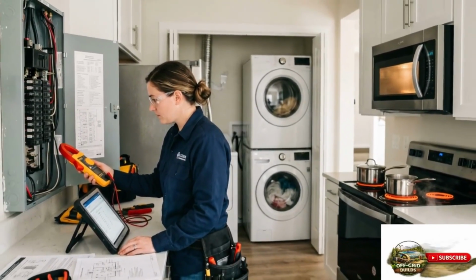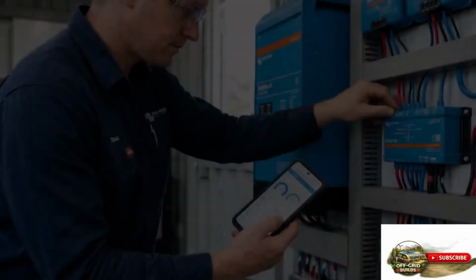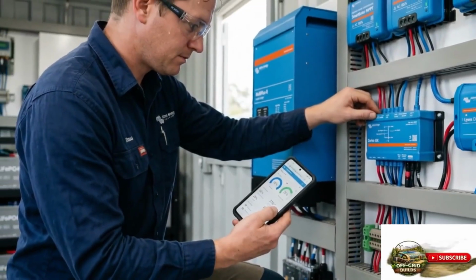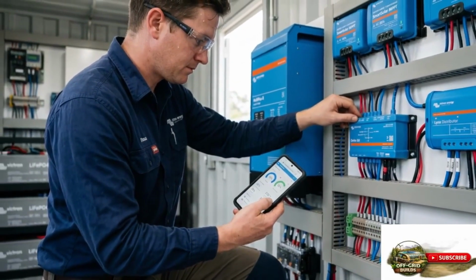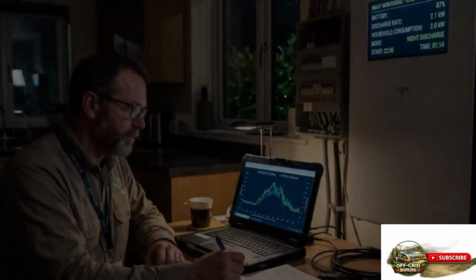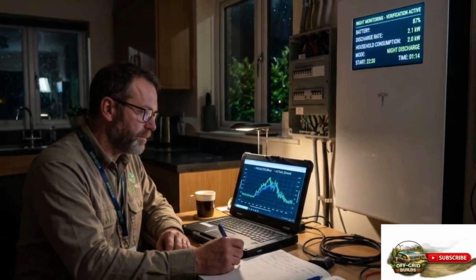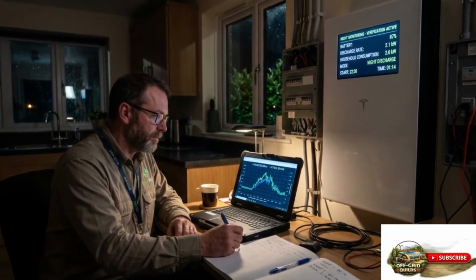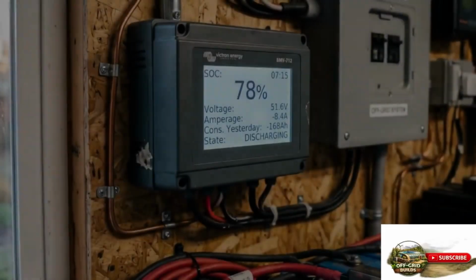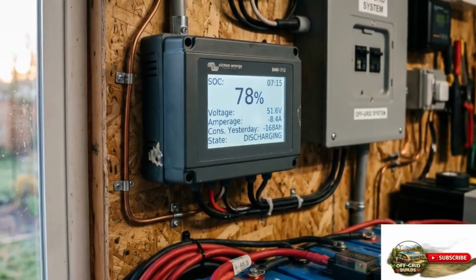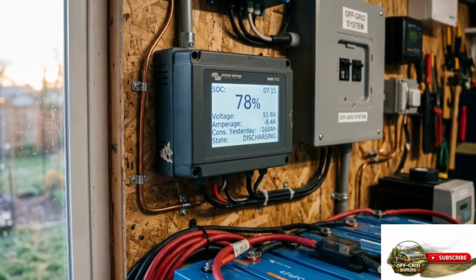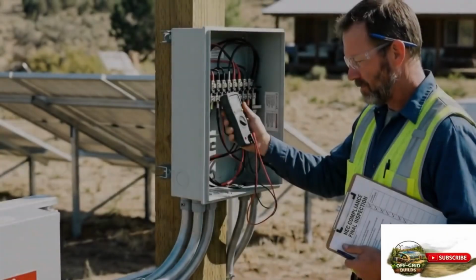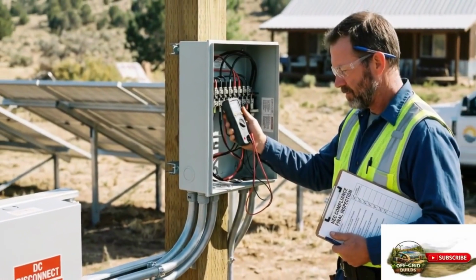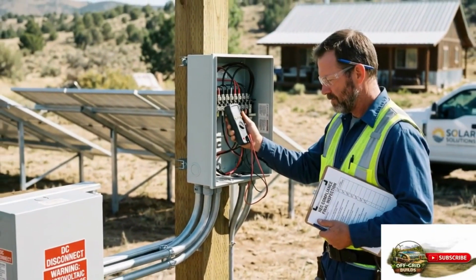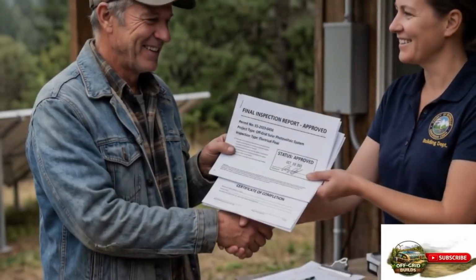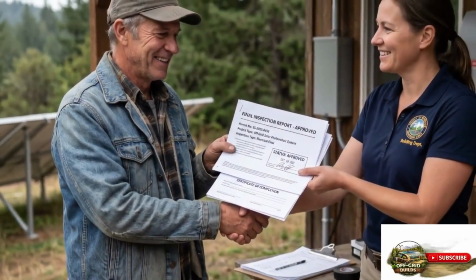Here is the mistake I promised at the beginning of this video, and it is responsible for more failed off-grid solar installations in 2026 than any other single error. It is not a wiring mistake. It is not a grounding mistake. It is a sizing mistake, and specifically, it is the mistake of sizing the solar array for average conditions rather than for worst-case conditions.